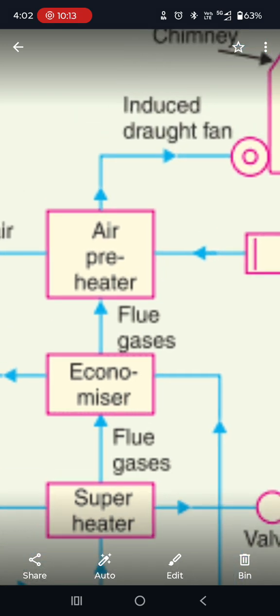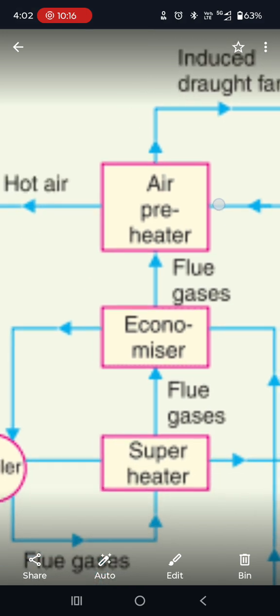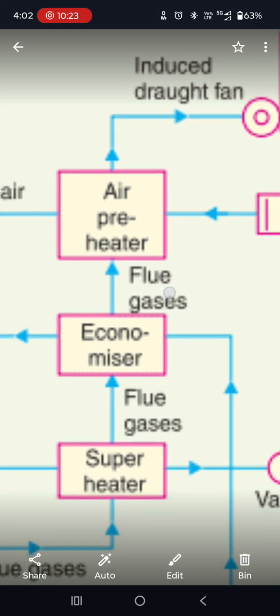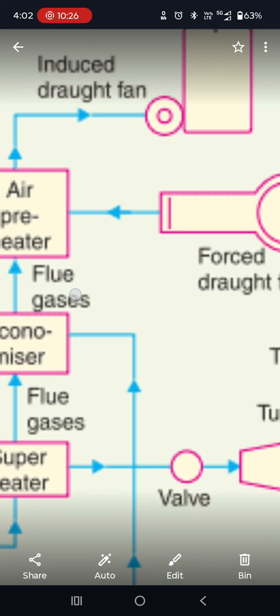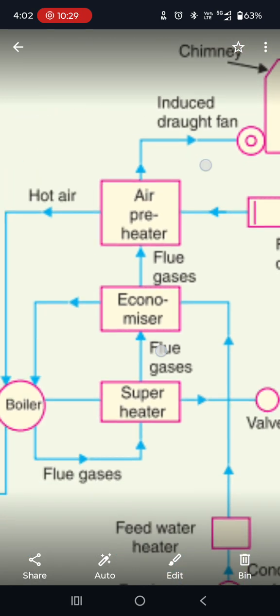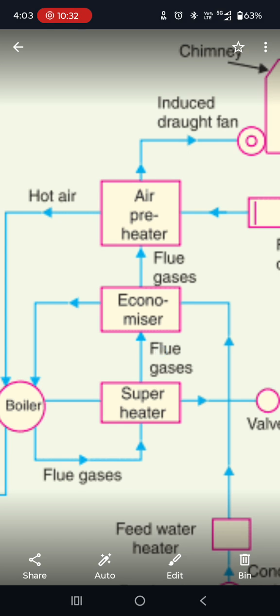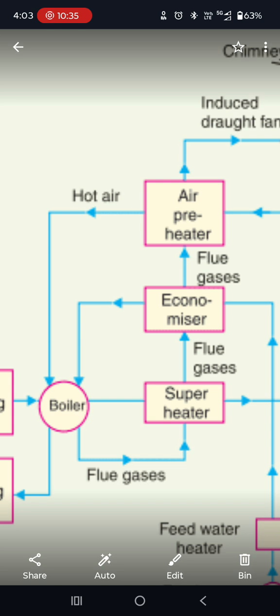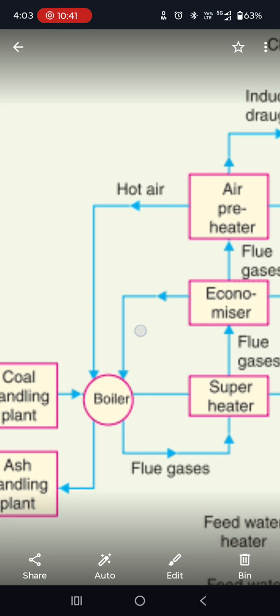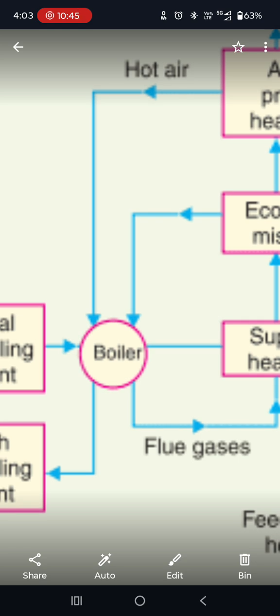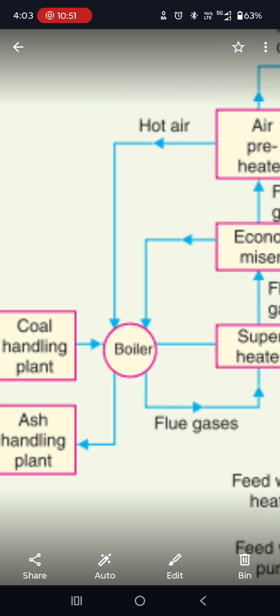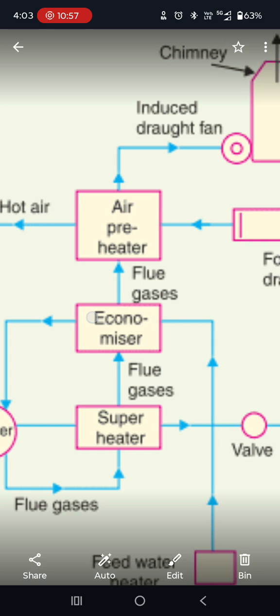Then we further utilize the temperature of the flue gases in the air preheater. The function of the air preheater is to suck the air from the environment, which is at normal temperature, and increase the temperature of that natural air so that this hot air can be sent to the boiler. As we know, we require air for the continuous burning of the coal. So with the help of this hot air, the burning of coal is uniform, and we can increase the efficiency.